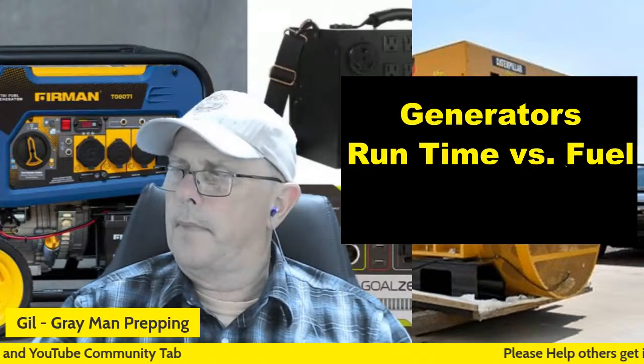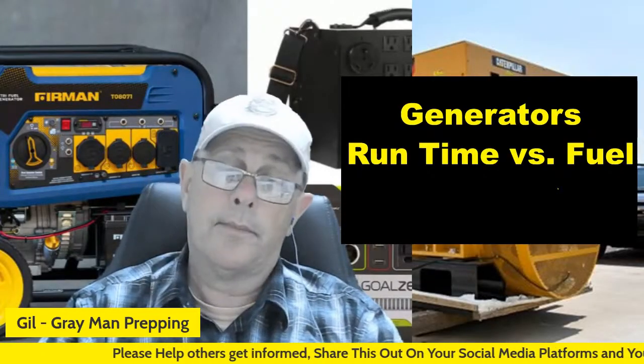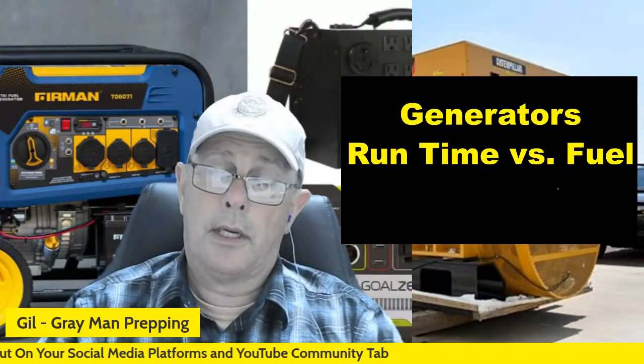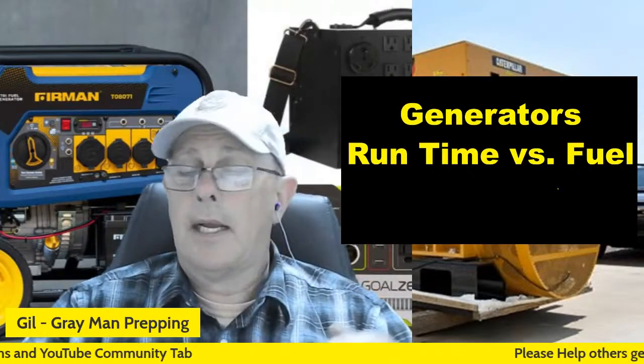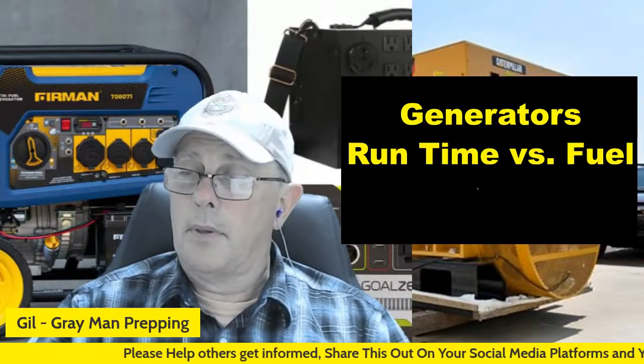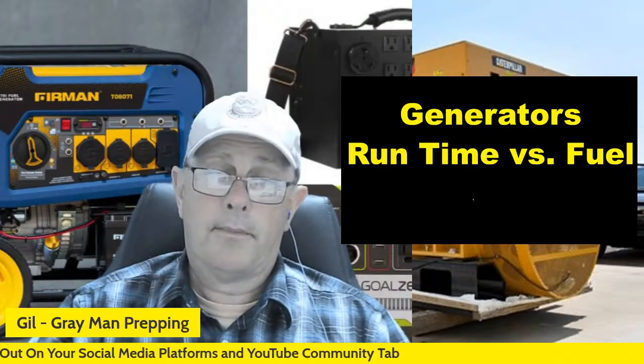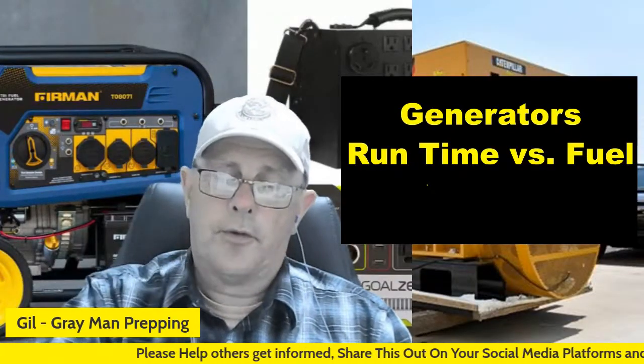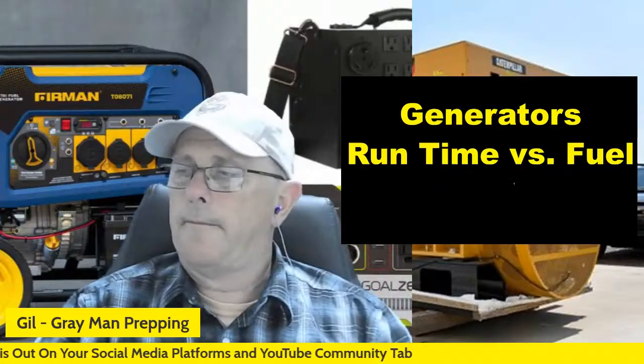All right. In your fuel usage, fuel is a problem because gasoline and diesel, for a diesel generator, the liquid fuels have a shelf life. You can put stabilizer or one of the other things into it to help extend its shelf life, but diesel and gasoline have a shelf life. Plus, if you have a gasoline or diesel generator, you're going to need to fire that sucker up once a month for a minute or two, just to get stuff flowing through it and make sure it stays lubricated, and to get the old fuel out of the gas line so you get fresh fuel in there. Just general keeping it up and running, testing type stuff.